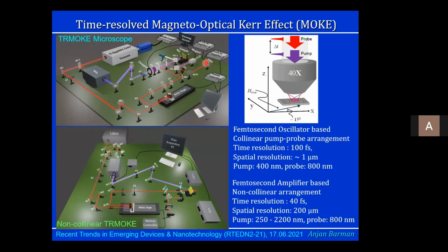And we use a very important detection technique, an optical bridge detector, which can measure extremely small Kerr rotation. So I was saying Kerr rotation, but this is not several degrees. In most of the cases, the Kerr rotation is of the order of several micro degrees. Especially in the dynamic regime, it is extremely small. So this system is able to measure that.